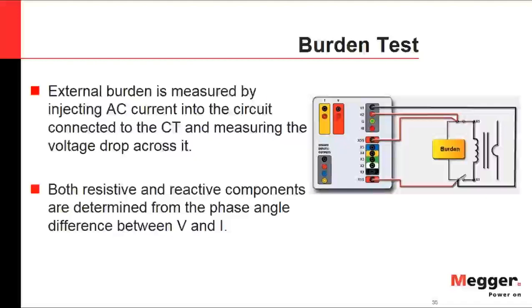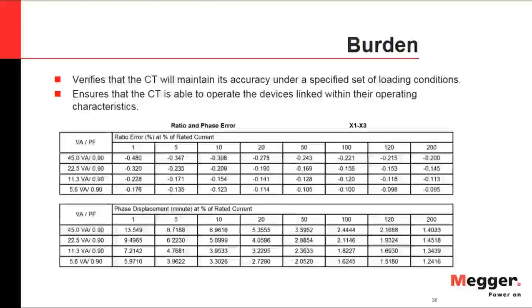The burden measurement is straightforward: connect the test set to the leads going downstream from the CT and measure directly the complex impedance of the burden. The test set then provides ratio and phase error information as a function of percentage rated current — from 1% all the way up to 200% rated current — at various VA levels such as 100%, 50%, and 25% of rated output.